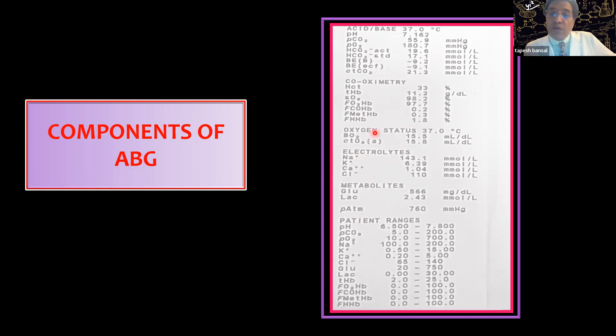Calibration of ABG has to be done six-hourly, and if you are in any doubt, recheck with the lab whether the ABG is being calibrated. Now moving on to temperature.